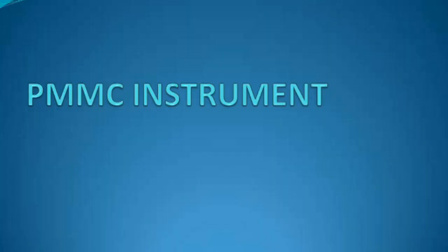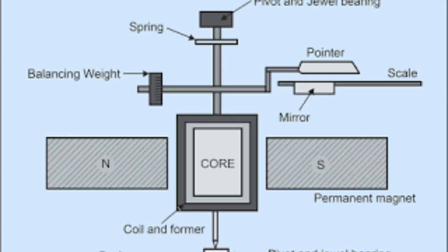The instruments which use a permanent magnet for creating a stationary magnetic field, between which the coil moves, are known as permanent magnet moving coil or PMMC instruments. They operate on the principle that a torque is exerted on the moving coil placed in the magnetic field of the permanent magnet. The PMMC instrument gives accurate results for DC measurement.